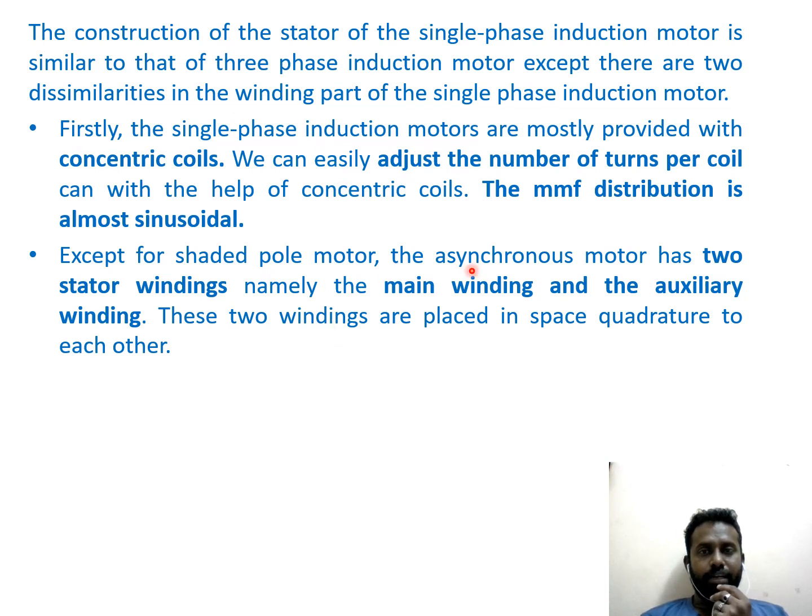This stator has main and auxiliary windings in the case of a single phase induction motor, whereas in a three phase induction motor you have only one winding, that is one three phase winding. The other point is that single phase induction motors are mostly provided with concentric coils in order to adjust the turns per coil.